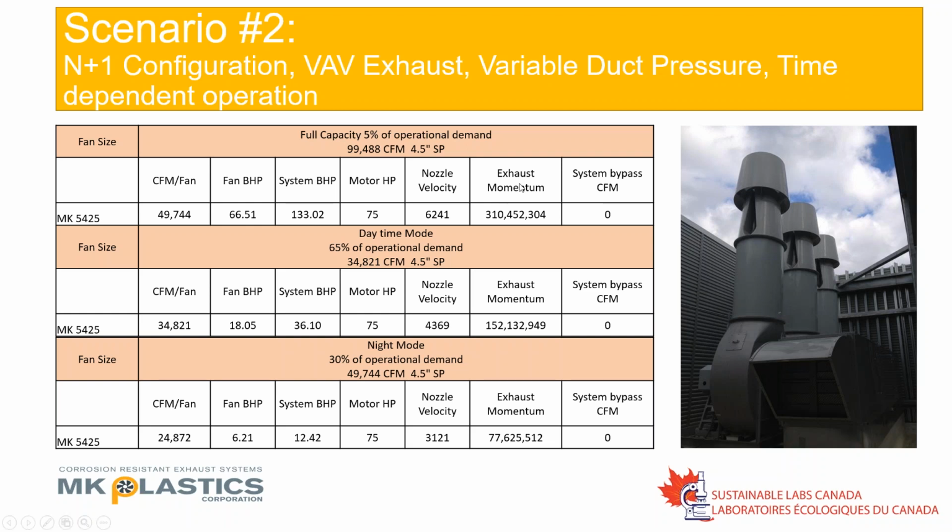The other thing I'll draw your attention to is I have here exhaust momentum. And part of why I put this here is because with plume height, there are two ASHRAE calculations. In fact, there's three, but the two I'm going to talk about are 2007 and 2011. And of those, there are 13 variations inside that calculation. So depending on how somebody calculates their plume height, they can make a plume height be of a certain height by that calculation. That doesn't mean it's necessarily going to meet it in your application, and the only test and balance work that is done is inside the building. So you need to protect yourself as engineers from this by saying, well, how do I check that if manufacturer A is telling me his plume height is 44 feet and manufacturer B is telling us that it's only 30 feet, how do I know which one is right?